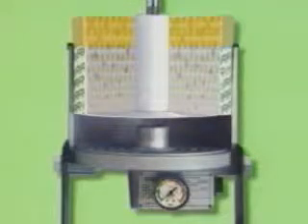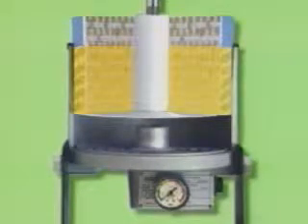For example, if there's a lot of steel fragments caught in the top of the filter, it's reasonable to assume there might be metal wear in the system. Rubber debris may indicate seal problems. If this stage had a finer filtration, it would quickly block up with contaminants. Instead, smaller particles can pass through from the top of the tapered pore to the second and third stages as the pores grow progressively more dense. Stage 2, the upper section, captures smaller contaminants as the pores become smaller. And Stage 3, the pressurized lower section, captures submicron contaminants in its densely compressed fibers.